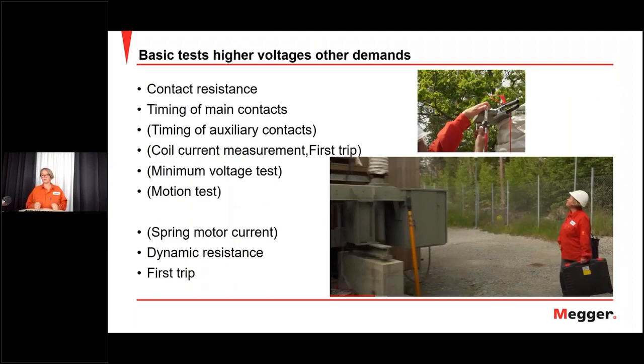Basic tests on the higher voltage SF6 circuit breakers create a little bit different demands. Of course, we measure contact resistance, we measure timing, auxiliary contacts, coil current, and when we measure coil current, if we measure first trip, we're going to talk about that later, it's a really, really important measurement. Minimum voltage test, of course, needs to be done, motion, spring motor current, but a specific test is things like dynamic resistance. On SF6, it's really important to know the status of the arcing contact, because if it gets burned down too hard, it will not be able to operate in the right way.